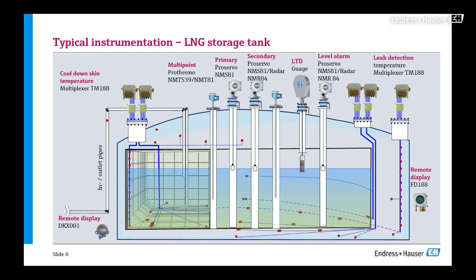Then the next one is what we call the cool down skin temperature. Very similar to the leak detection. The only difference on this one is the location where the skin point is installed. With regards to cool down skin temperature, it is installed inside your LNG tank, where the liquid is.